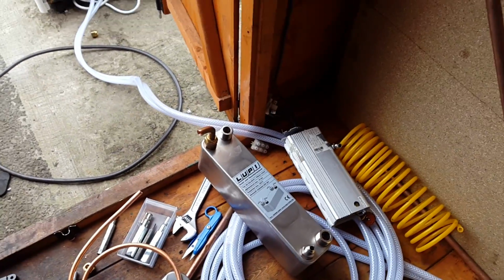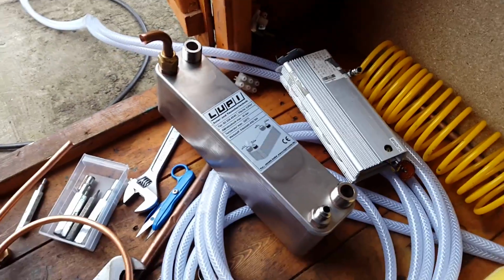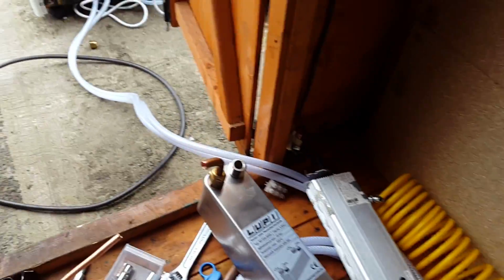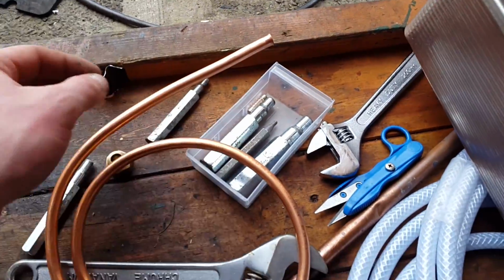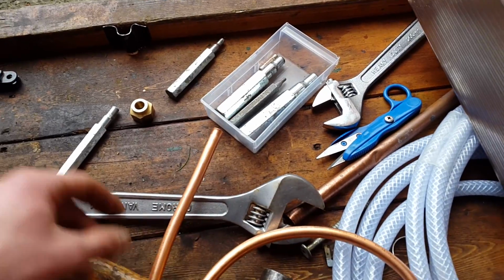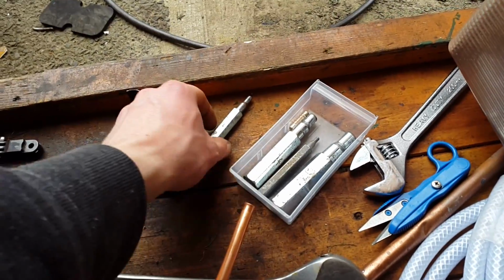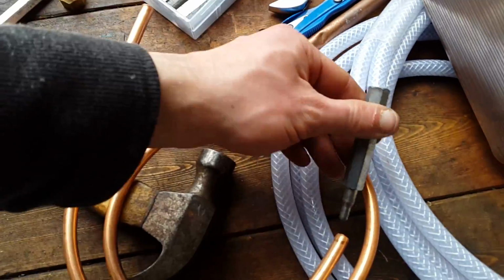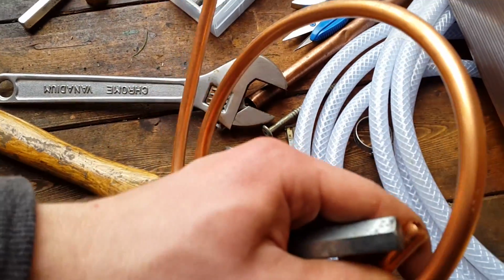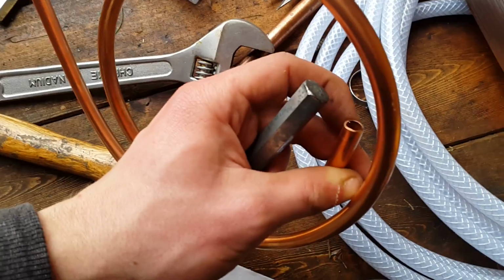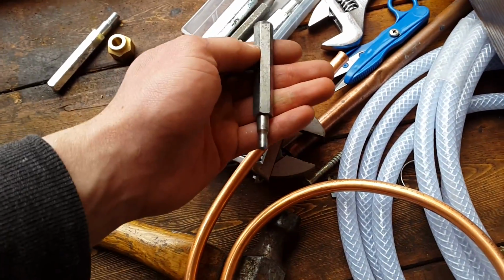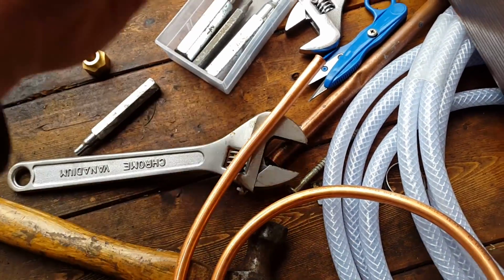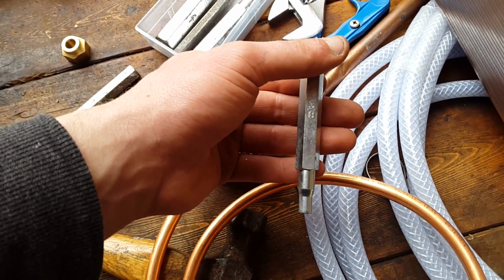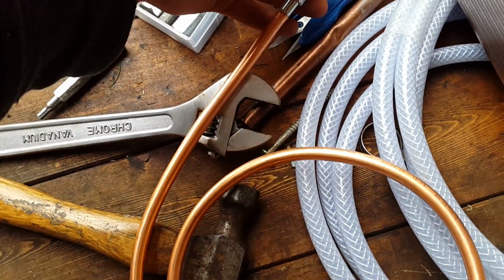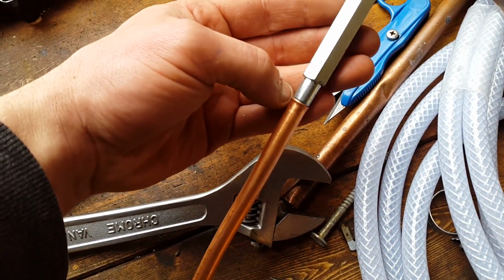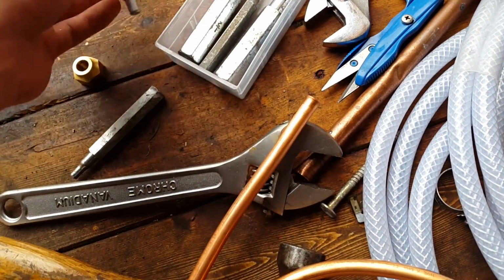As for the exchanger, I've got the first flare made, and the way I make the flares is using these punches here. I used the 5/16 one just to straighten out the end of the tube, to take off that inward-facing burr from when it was cut at the factory. Then I move up to the 3/8 flare and just bang it in until it flares out like that, then move up to the bigger one.